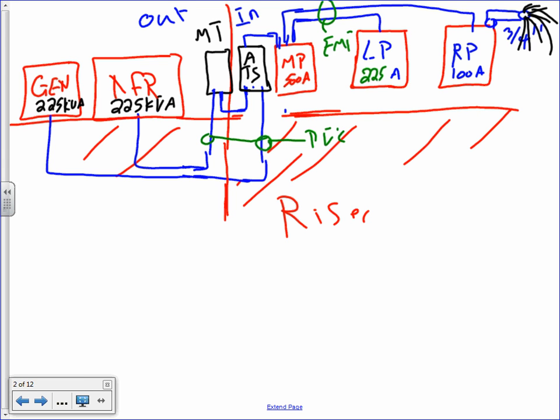Now, your auto transfer switch you're going to drop tomorrow, the auto transfer switch, which is that boy here, is going to be also 500 amp. Most likely it's going to be a 600 amp because we don't have a 500 amp. Everybody has the sizes that you need? All the sizes that you need for the riser? Any question about the riser that we need to drop tomorrow?